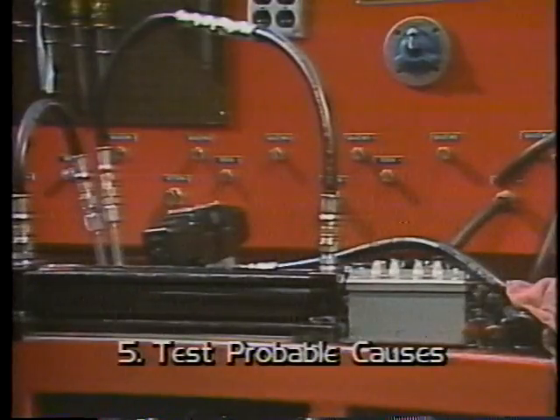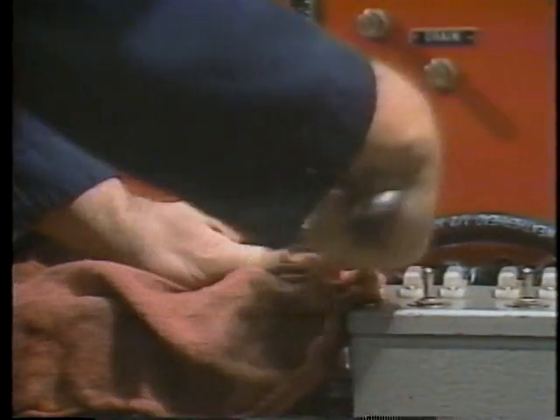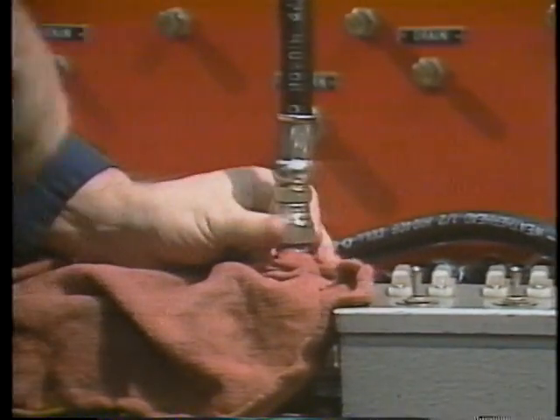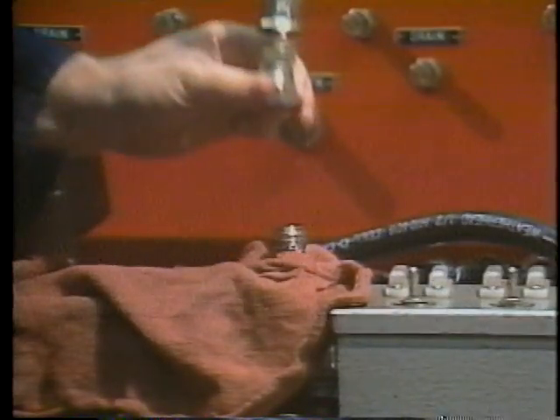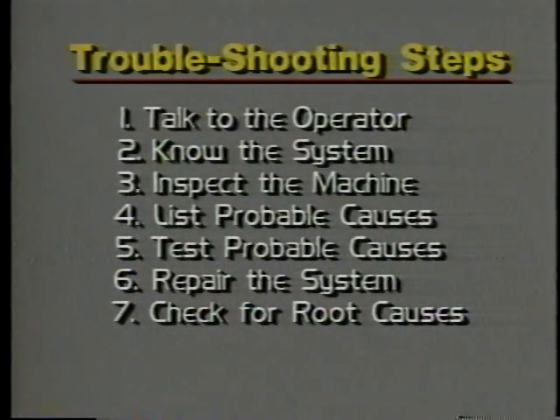After performing all these quick checks, if no obvious problem has been found, we'll need to go further — listing the probable causes that still remain, such as an obstruction in a valve port or a hidden mechanical problem in the cylinder, and testing them by breaking some lines to check system flow more closely, or by replacing components. But by looking for obvious causes first, we've probably saved ourselves a lot of needless time. In almost all cases, we would already have discovered the trouble. Always start with the procedures that take the least time and effort. In later lessons we'll troubleshoot more complicated systems requiring more detailed inspection, but the principles remain the same.